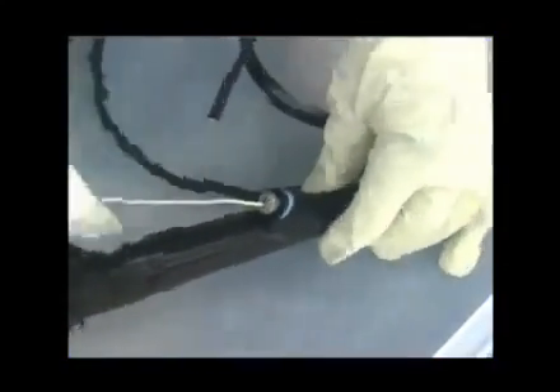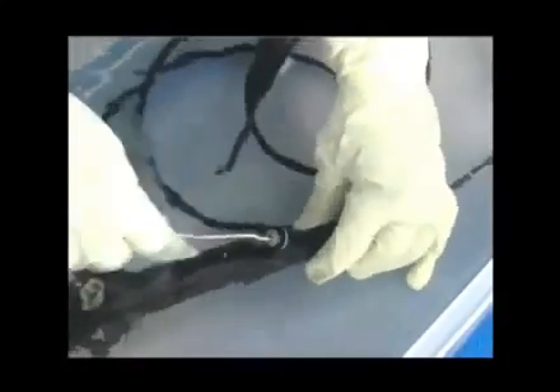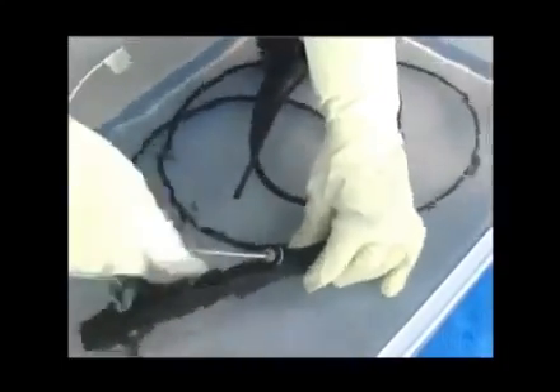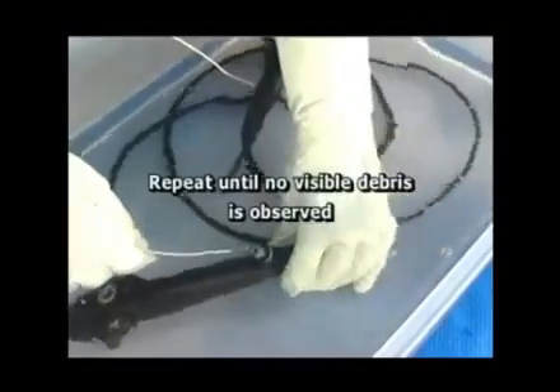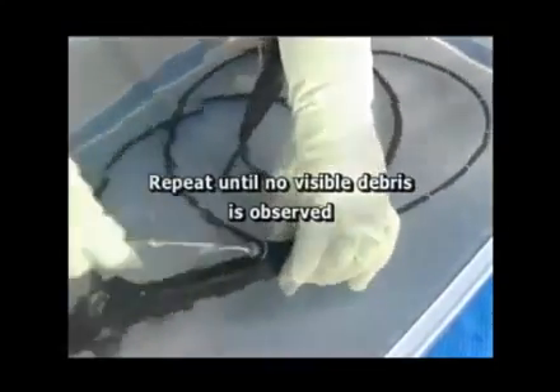Next, insert the channel brush into the instrument suction port. Pass the brush through the insertion tube until it emerges from the distal tip. Clean the bristles and retrieve the brush. Once again, clean the bristles, and repeat until no debris is observed on the brush tip.